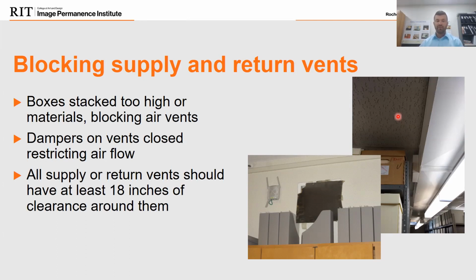And when that heating coil failed, we now have really cold, really damp air that's coming down this ductwork into the boxes that don't allow that air to mingle in the space. We've had instances where mold has just covered this box, materials within the box and below. So you want to make sure we're giving that air some chance to move and mingle, because in the event of a failure, you can have some really significant issues if you don't catch that failure in time.